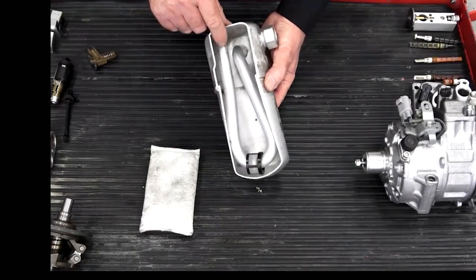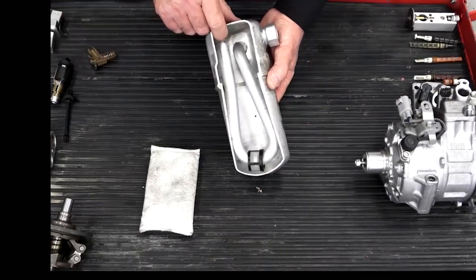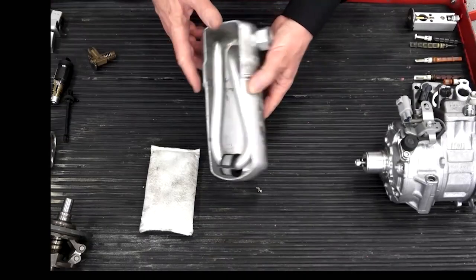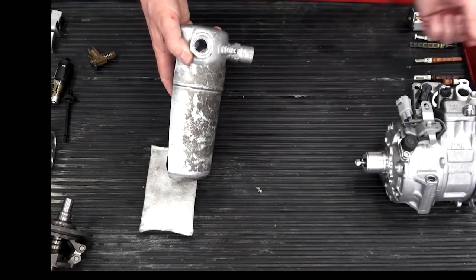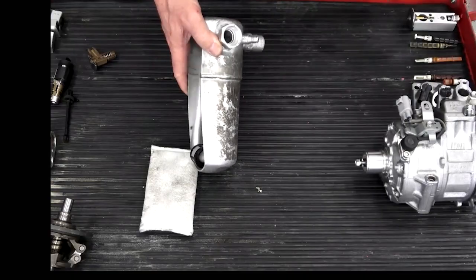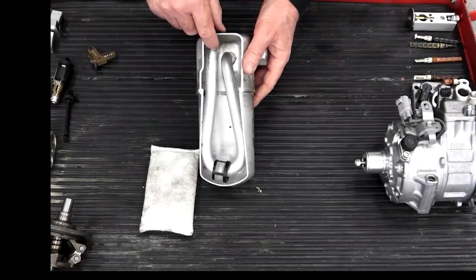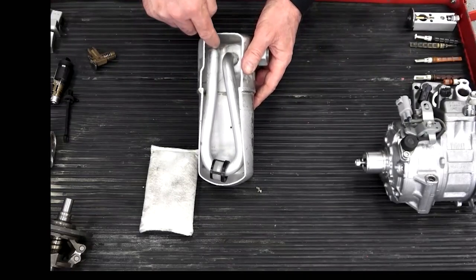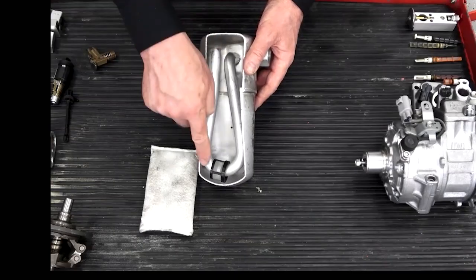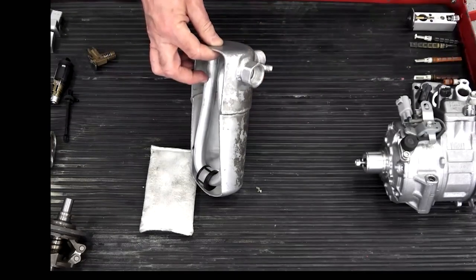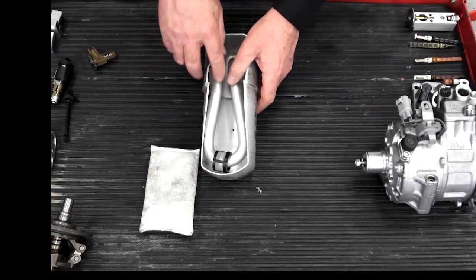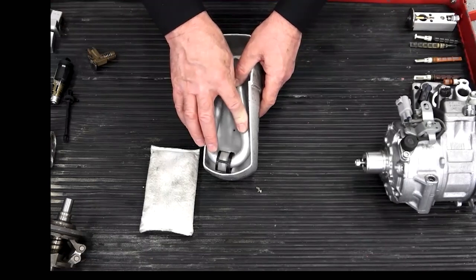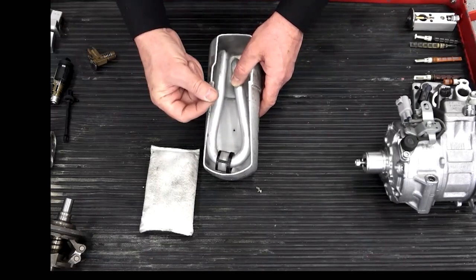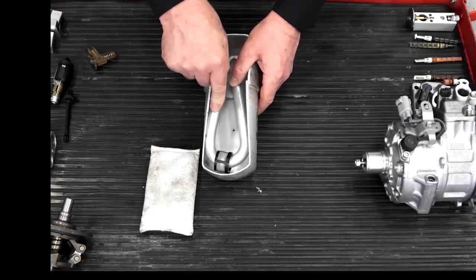It reaches almost at the top, not quite, but almost at the top of the can, and this end of it is connected back to the compressor. This is the suction line going back to the compressor. So the compressor is drawing refrigerant gas from the top of the can down this J tube and back out to the compressor. Now, as the gas is drawn down the J tube, it creates a Venturi effect, a low pressure area in the J tube.